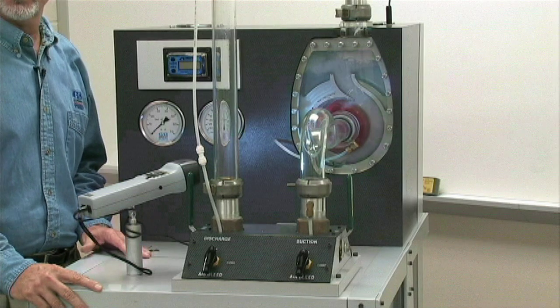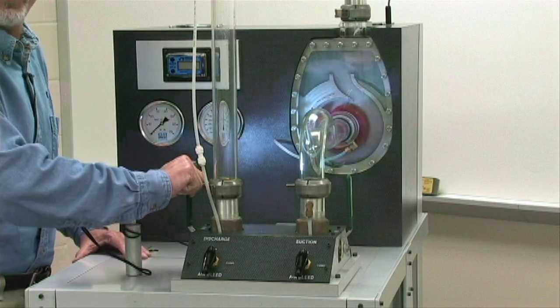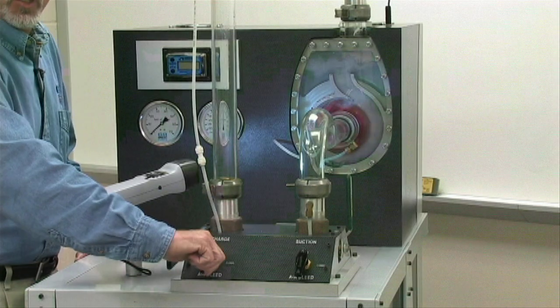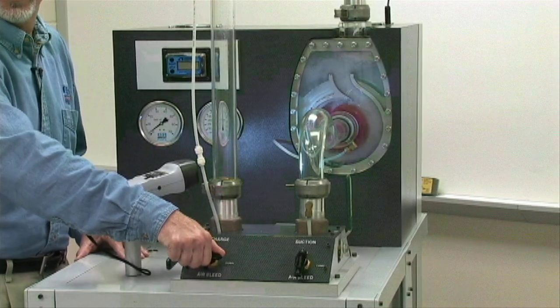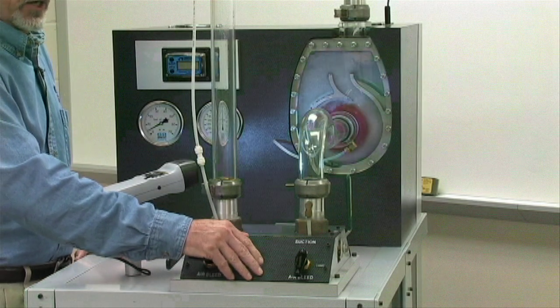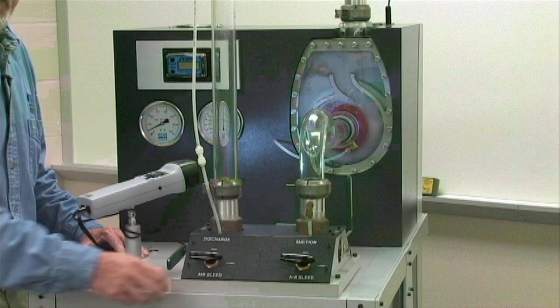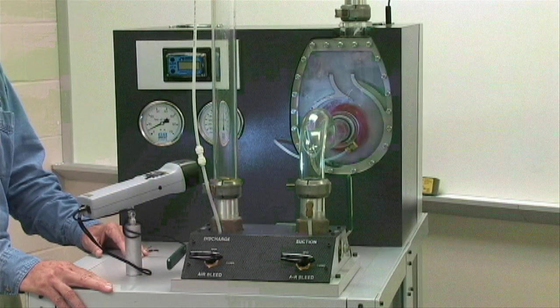Let's demonstrate this by closing off the discharge valve and closing off the air bleed line on the discharge side. By closing the air bleed line on the suction side, we will now allow the pump to attempt to prime, but it fails to do so due to air binding.